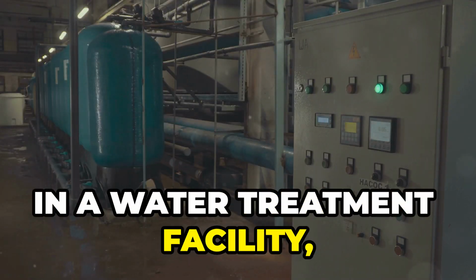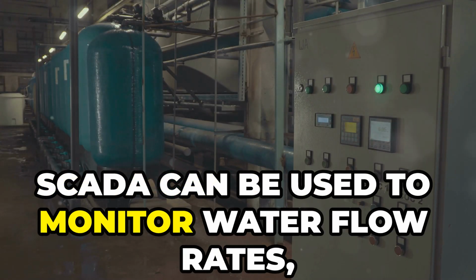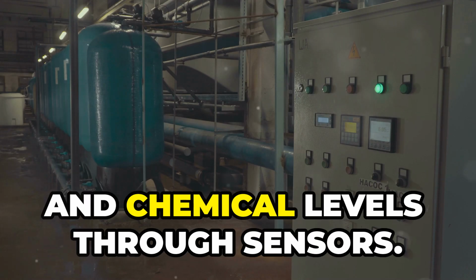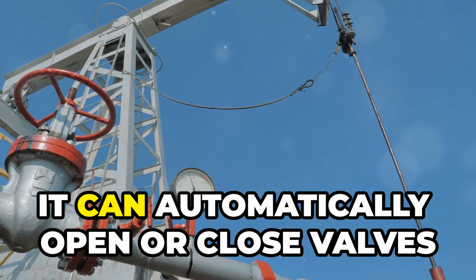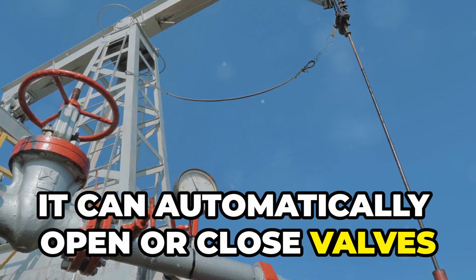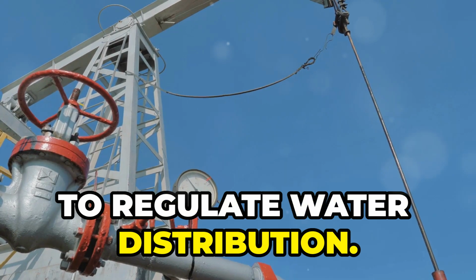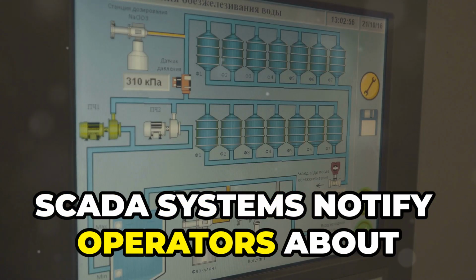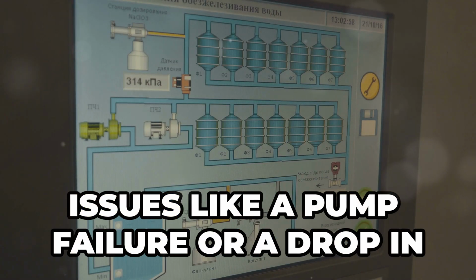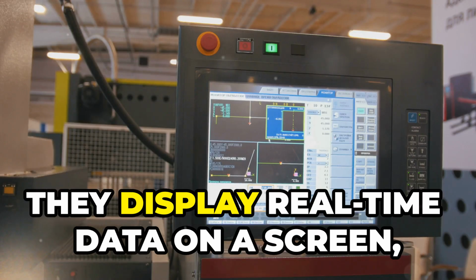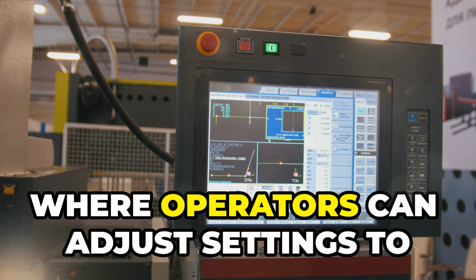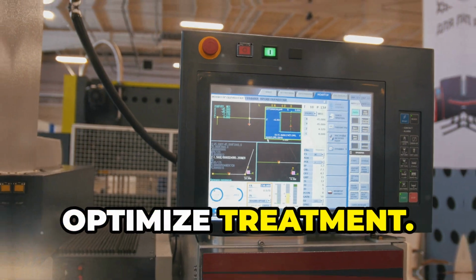Example 1. Water treatment plant. In a water treatment facility, SCADA can be used to monitor water flow rates, pressure, and chemical levels through sensors. It can automatically open or close valves to regulate water distribution. SCADA systems notify operators about issues like a pump failure or a drop in water quality. They display real-time data on a screen where operators can adjust settings to optimize treatment.